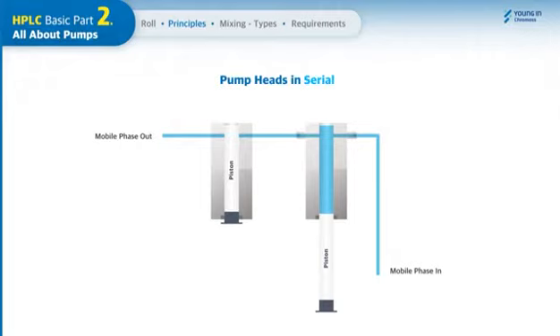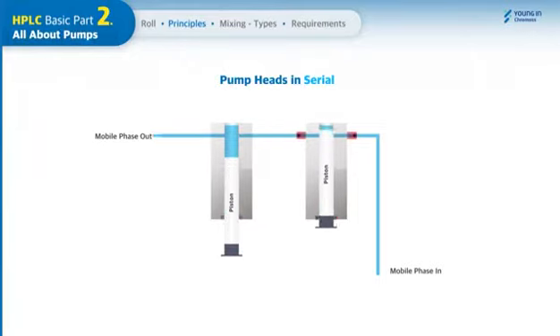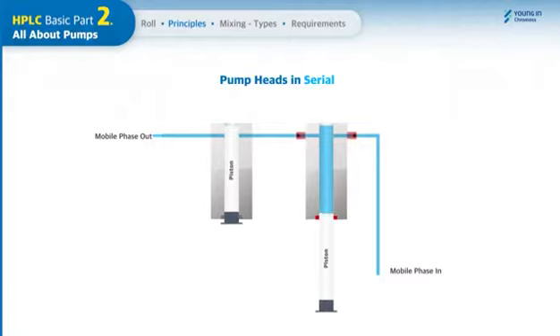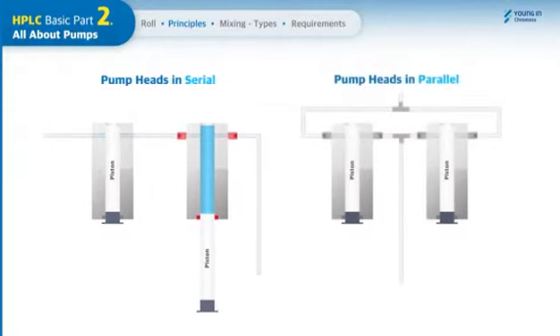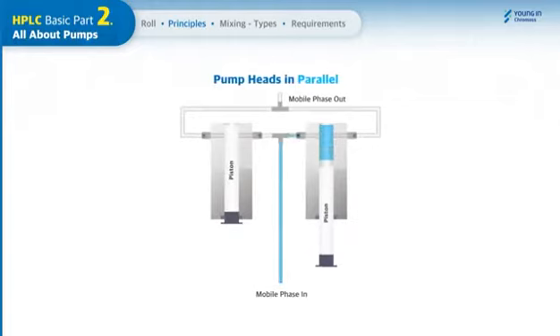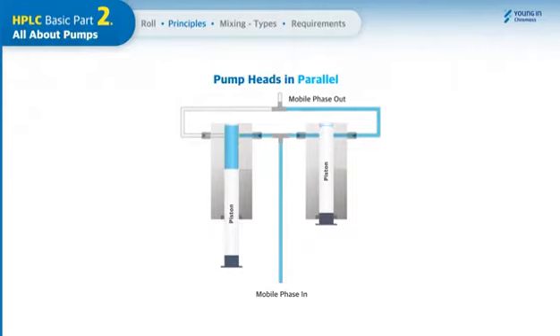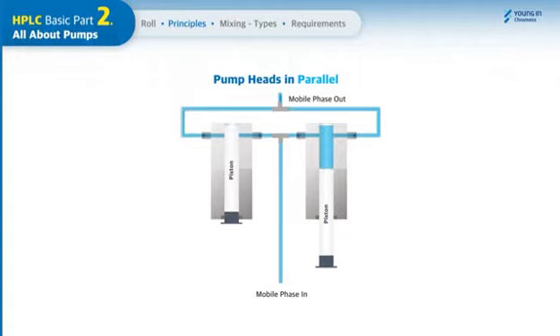Although pump heads in serial have only one pair of check valves, the primary piston needs to run twice the operation cycles to refill the secondary pump head, which makes the workload twice and results in the wear of parts such as check valves and piston seals. In a parallel pump, both pistons independently work to draw the mobile phase, in turn, to deliver it at a programmed flow rate. Although the parallel pump requires two pairs of check valves, it delivers pulsation-free flow that can reduce the wear on the consumable parts.